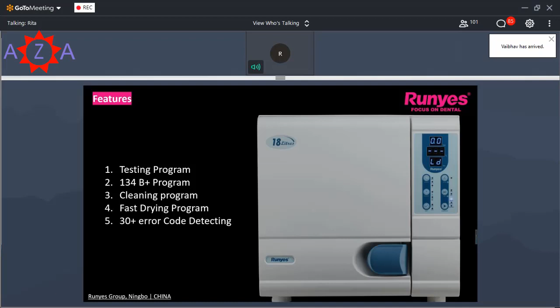Faster drying program. The standard drying time of the RUNYES autoclave is 10 minutes. But if sometimes the clinic needs emergency use, we also have 1 minute or 5 minutes as options to shorten the cycles. And another feature is we have a 30 error code detecting program. So it's very convenient for the engineer to check the issue easily. Okay, so this is the program overview. I introduced the details.